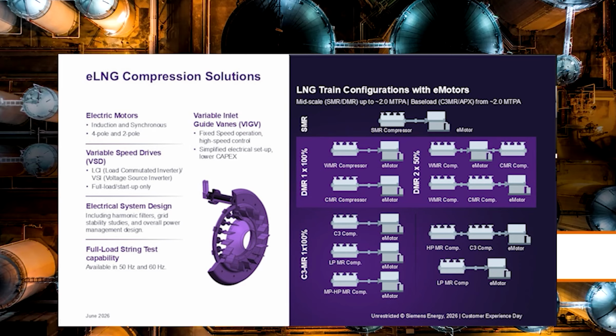And you can see on the right side some of these other processes, how that would look with motor-driven compression. The single mixed refrigerant process is a single compressor with direct drive or gearbox and motor. And then we have dual mixed refrigerant with two different embodiments here, where you can combine and do a 2x50 design or 1x100 design for both types of refrigerant blend that you need. And then finally, the C3MR process, which is the one that Woodfibre has selected for their project.